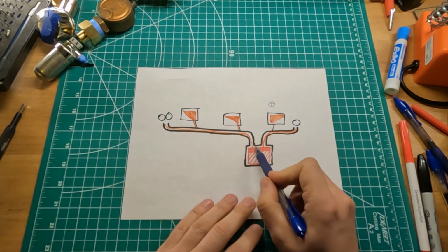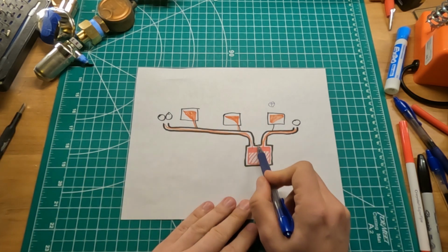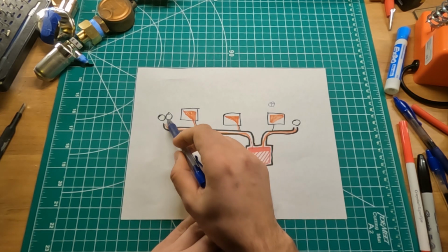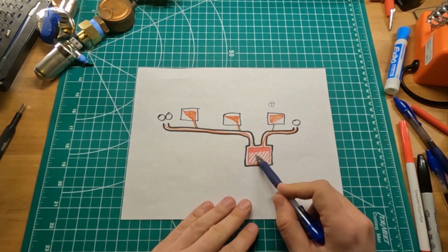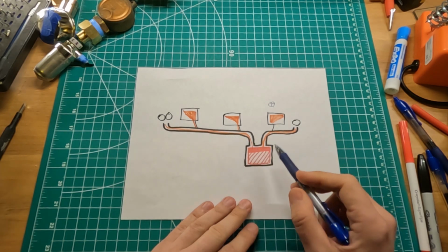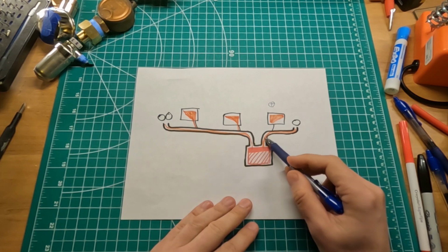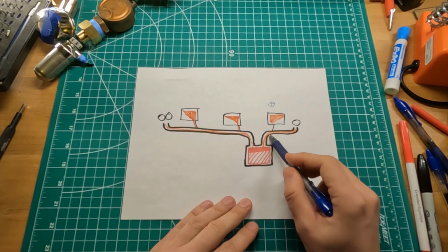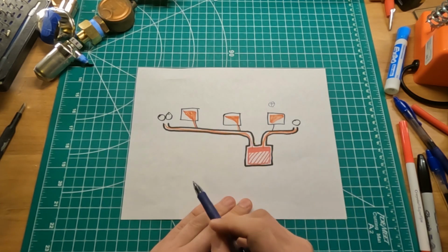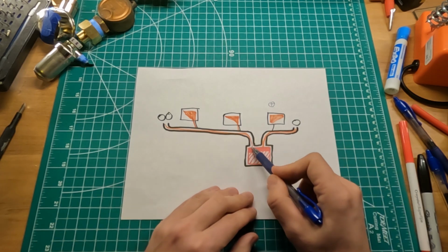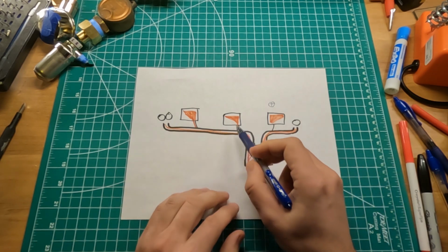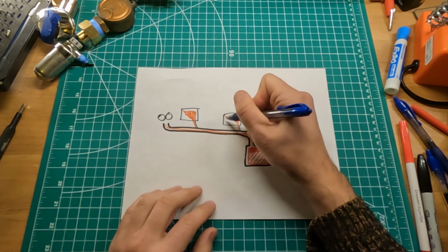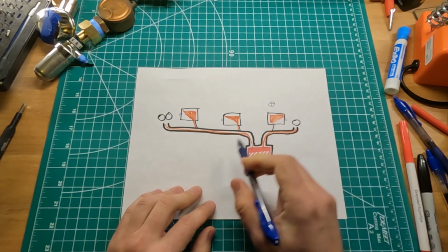cleanly like that. That is, by the time this main steam hits those mains, the boiler probably produces quite a lot more steam than when it started out. So because of that, it probably has the ability to keep on pushing the steam in this direction as well, so that this leg might get filled up with steam even before those radiators get totally filled up. But again, because there's tons of steam produced by then, the steam cannot go anywhere else other than to the vents on those two radiators, and this one as well.